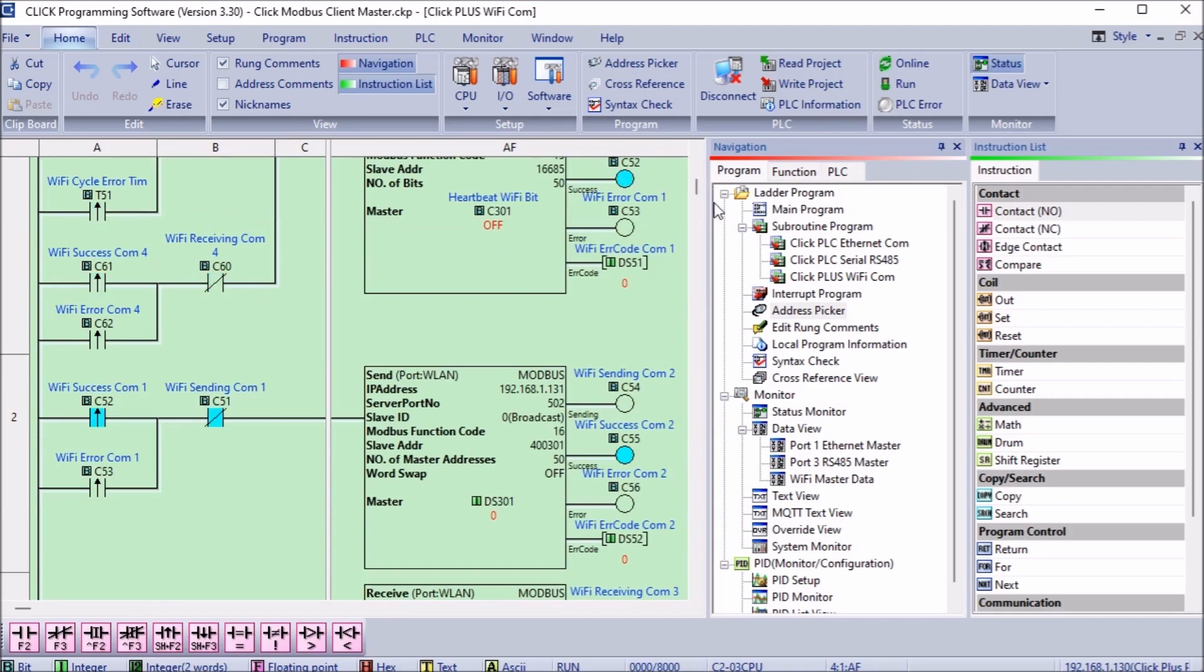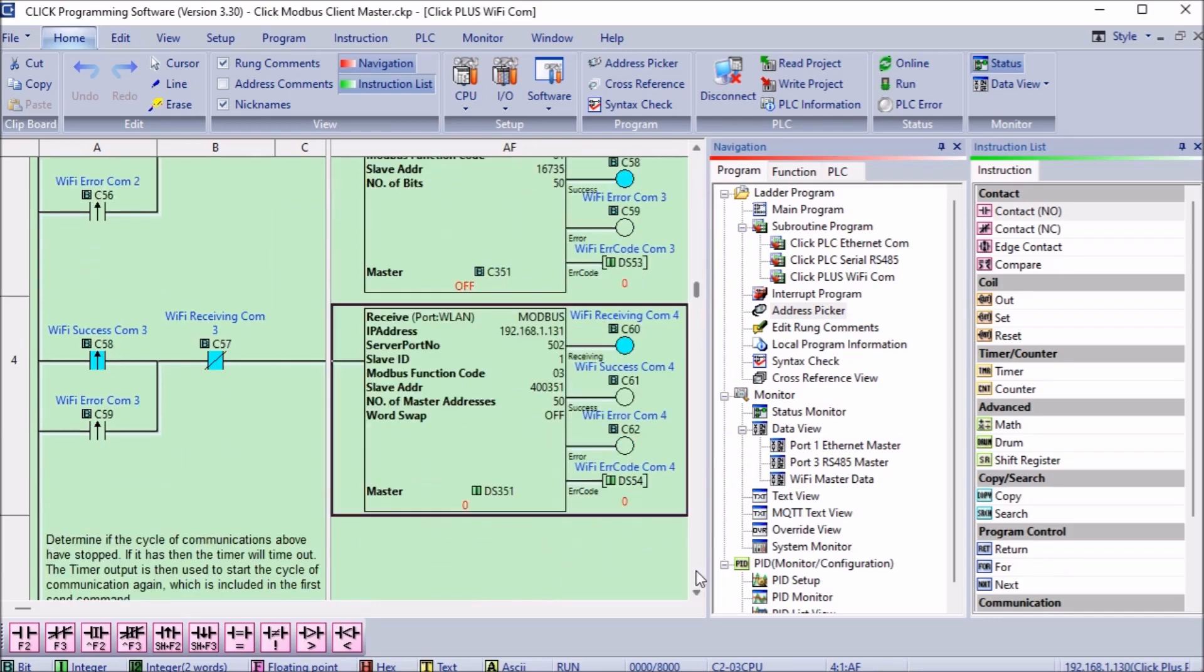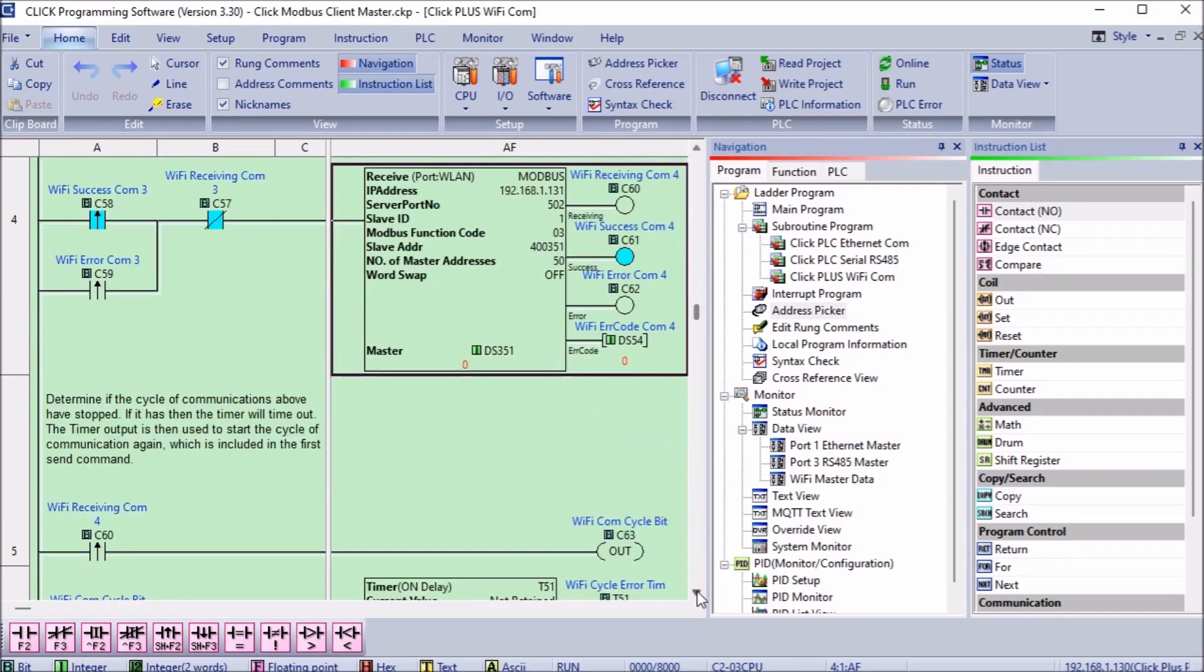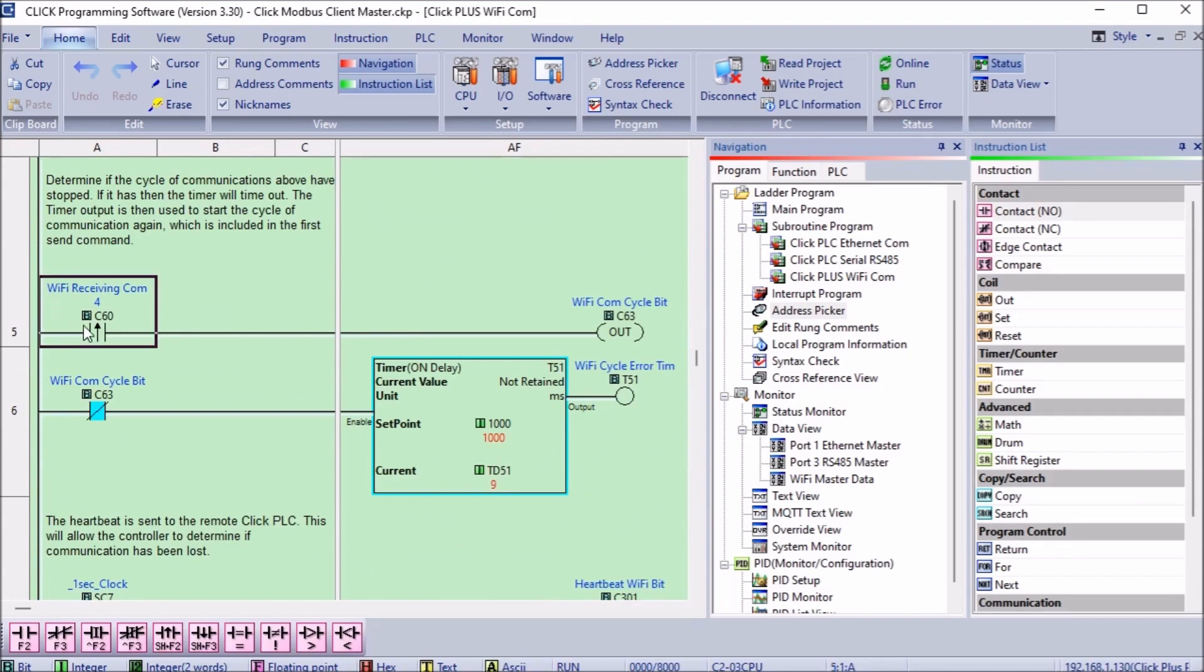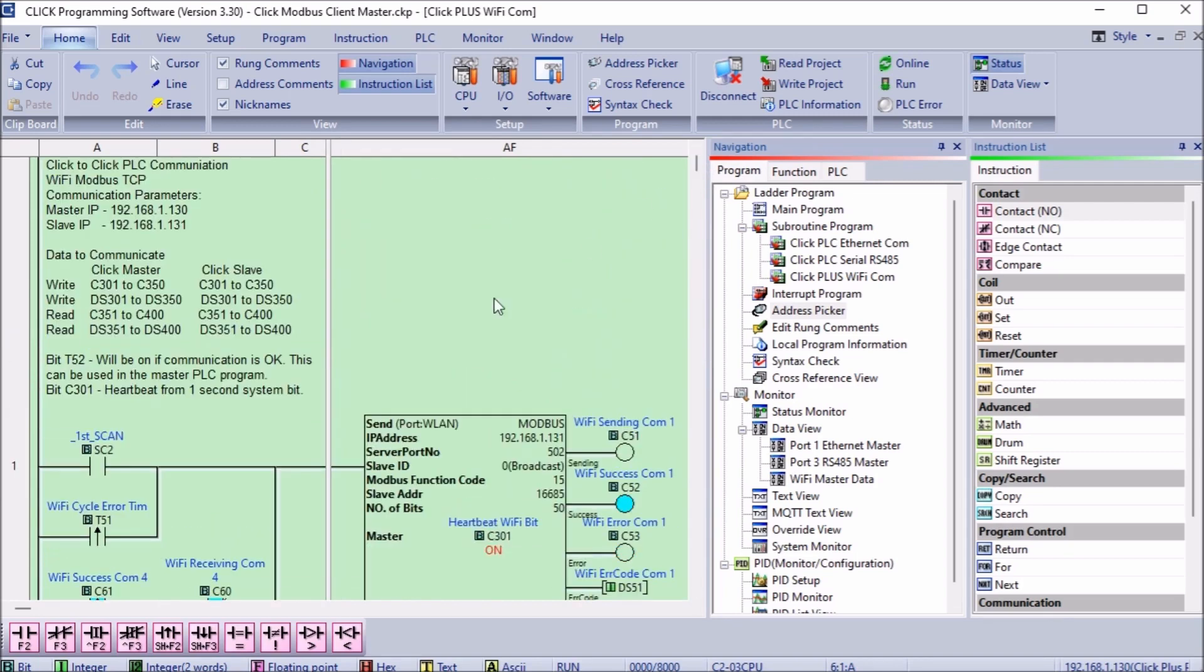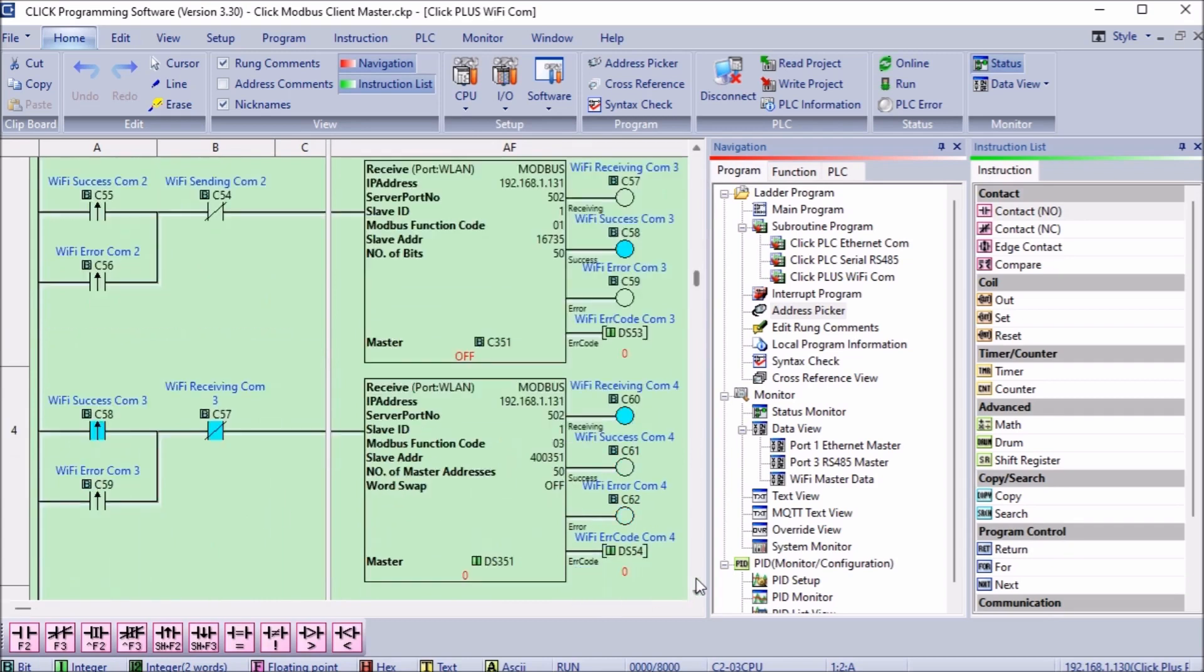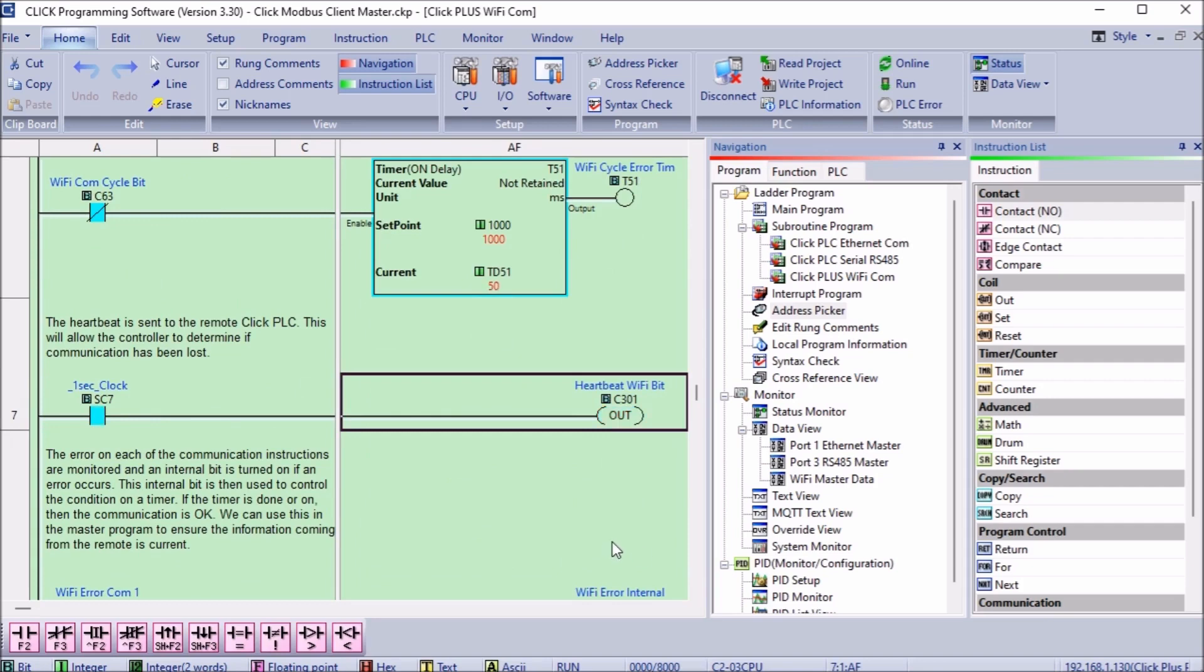The sending and receiving cycles use the flag bits. If this cycle stops we need to start cycling again. The leading edge of the last receive instruction triggers an internal bit. The normally closed of this bit will start a timer set for a thousand milliseconds or one second. The leading edge of this timer bit will then start under the first scan flag on the first rung. We will now ensure that the information will continue to be updated. A heartbeat is sent to the first bit we write to the click server PLC. This is used to tell the server if communication is still active. Even though we're cycling above with our commands, it may not mean that the information is being sent. There could be errors on a line and the server PLC will need to know this and react.